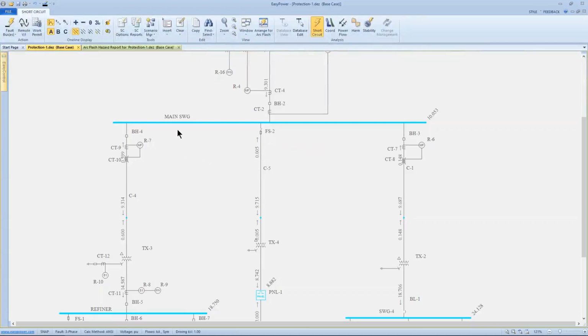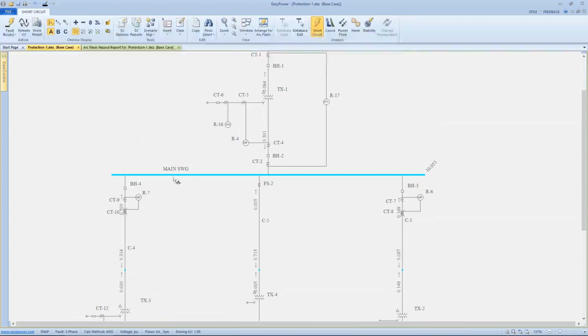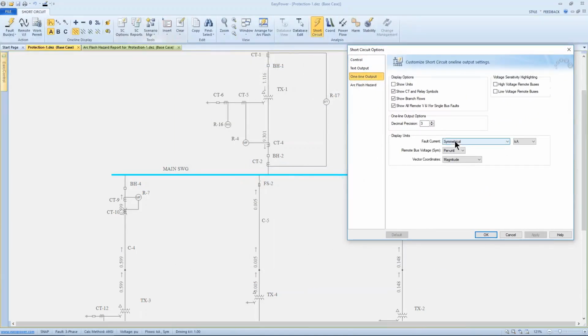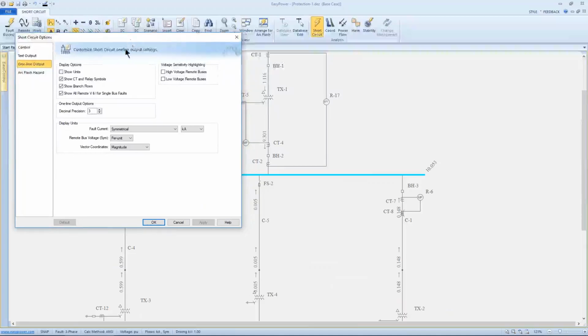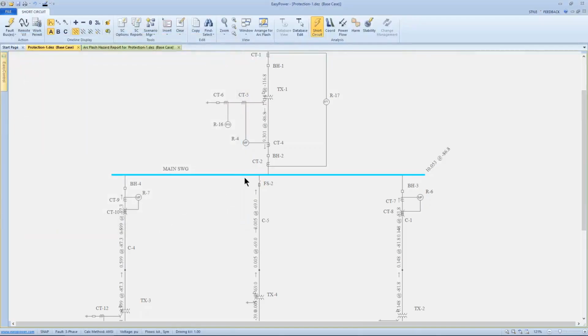The contribution current, in this case, will be coming 9,300 amps from upstream, 600 amps, 5 amps, and 148 amps. And again, this is a case where this particular totalized short circuit current may not equal the sum total of each of these currents. The reason for that, if I go into short circuit options, I can control what's displayed on my one line. On the one line output, we're showing symmetrical current, and right now we're only showing magnitude. If we display the magnitude and angle, we can see that we will get an accurate vector sum of the different currents coming into this particular fault.